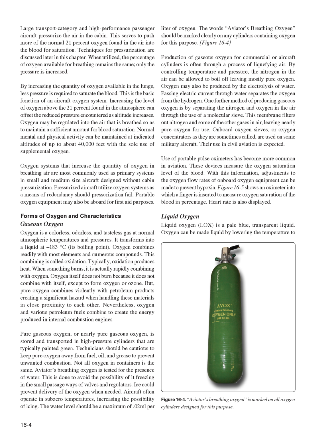Use of portable pulse oximeters has become more common in aviation. These devices measure the oxygen saturation level of the blood. With this information, adjustments to the oxygen flow rates of onboard oxygen equipment can be made to prevent hypoxia. Figure 16.5 shows an oximeter into which a finger is inserted to measure oxygen saturation of the blood in percentage. Heart rate is also displayed.